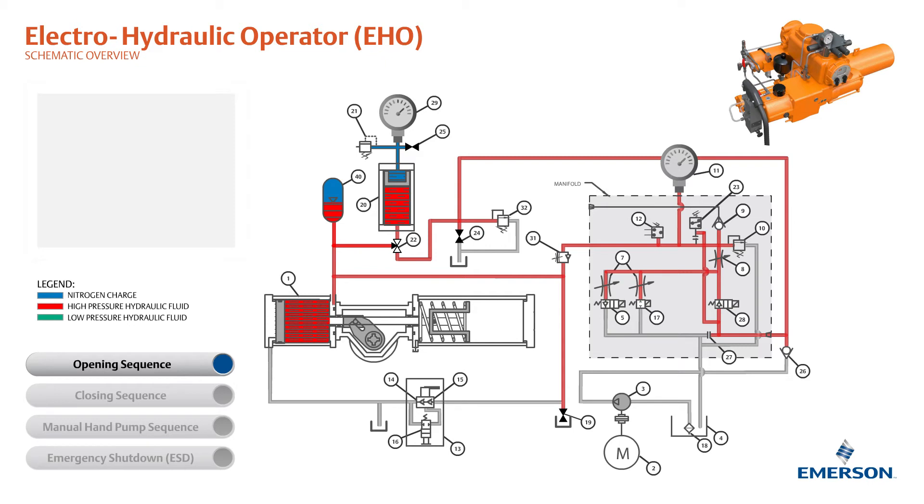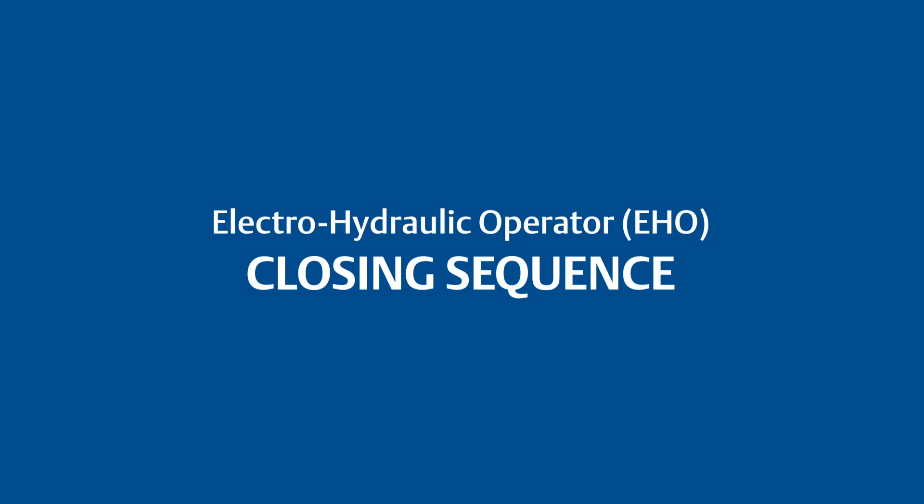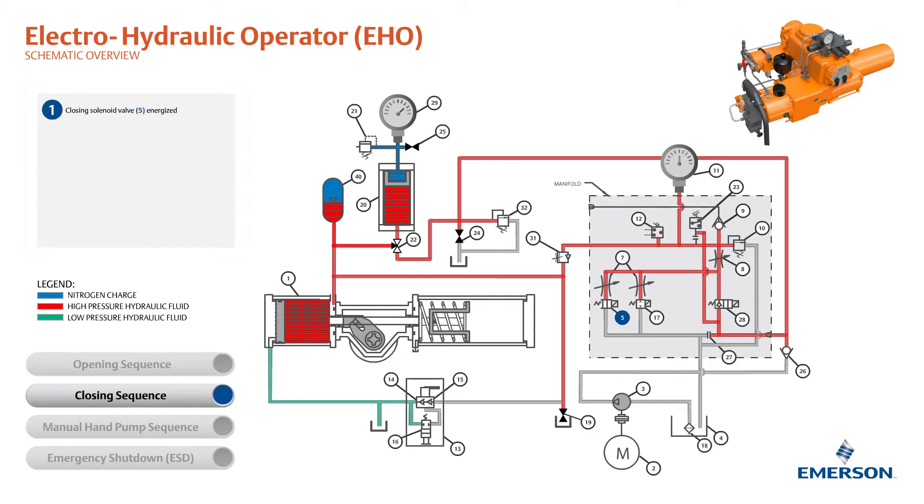The accumulator is recharged and ready to be used for the next opening sequence. This is the theory of operation for the closing sequence of the Bettis EHO. The closing solenoid valve is energized. The high-pressure fluid flows out of the actuator's hydraulic cylinder through the closing solenoid valve and into the reservoir.